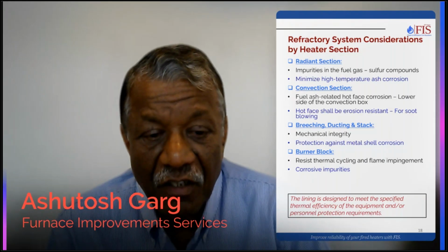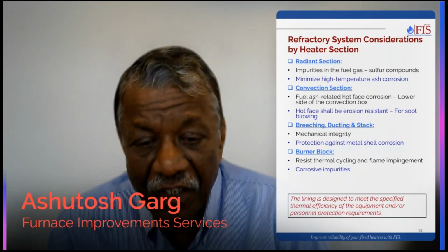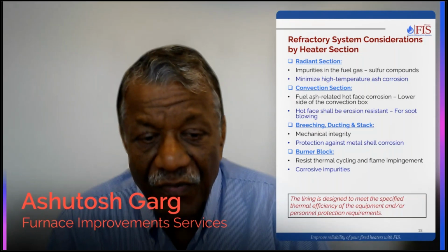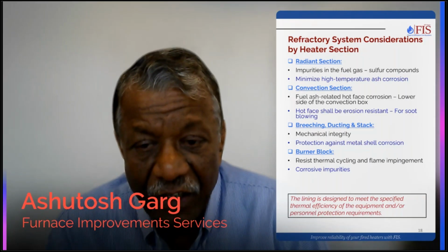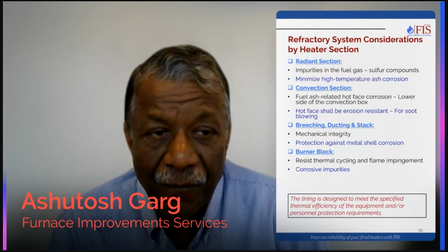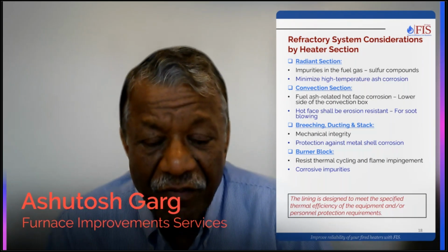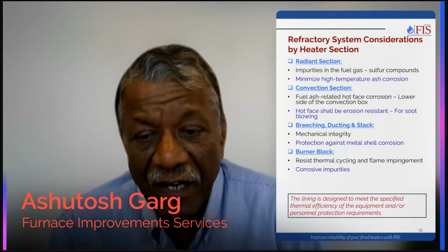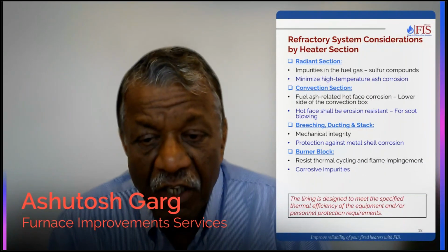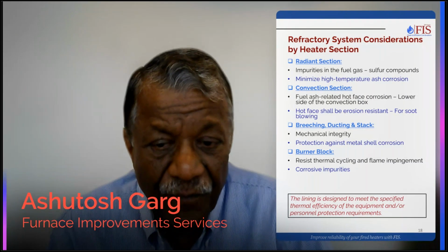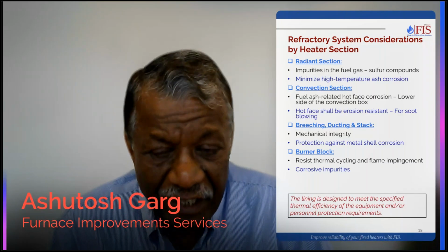But in other places in the world, fuel oil firing continued for a long, long time. And fuel oil firing is very, very tough. Fuel oil has sulfur, fuel oil has sodium, fuel oil has vanadium.